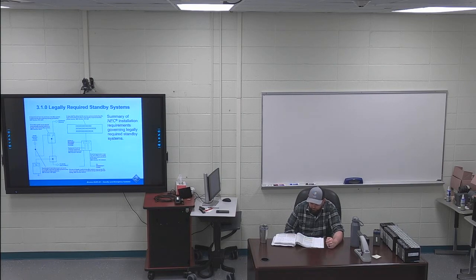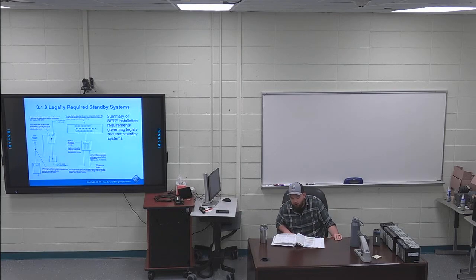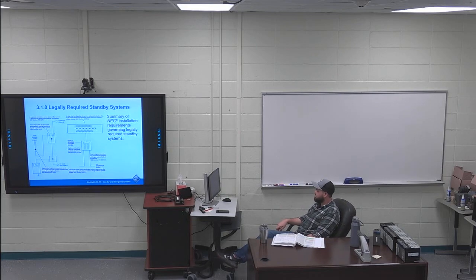Skip that little one-sentence paragraph, and the whole next paragraph is highlighted. You have two different questions come out of this one paragraph. Just key in whenever I'm keying in on certain sentences. In general, legally required standby systems are typically installed to serve loads such as heating and refrigeration systems, communication systems, ventilation and smoke removal systems, sewage disposal and lighting systems, and industrial processes that, when stopped during any interruption of normal electricity supply, could create hazards or hamper rescue or firefighting operations. So you're going to have all different types of stuff that has to stay on emergency power.